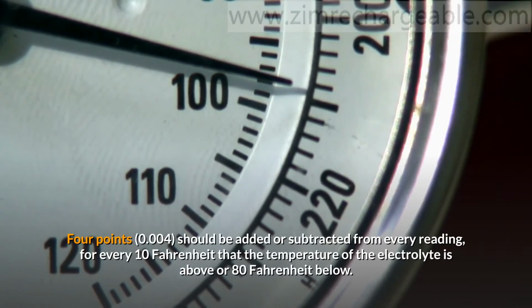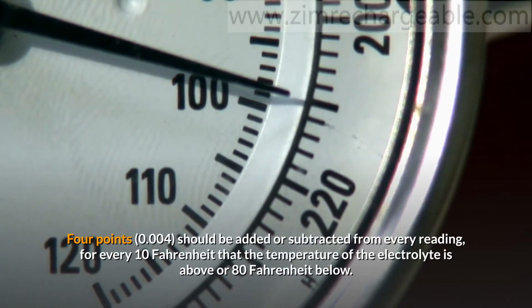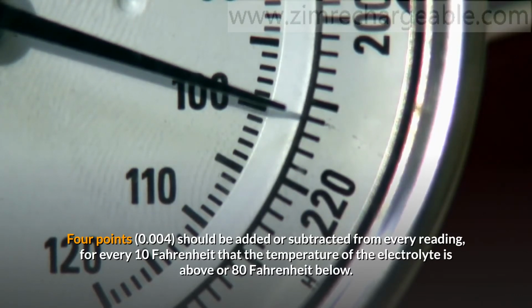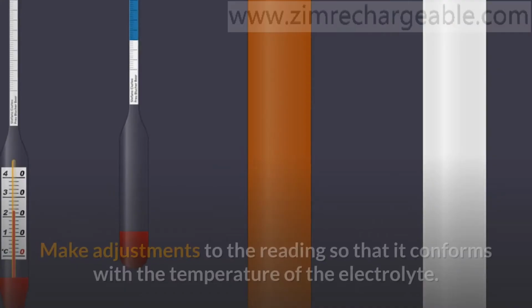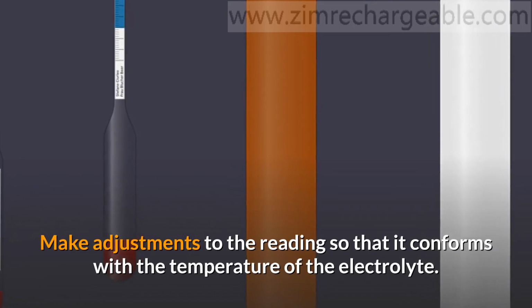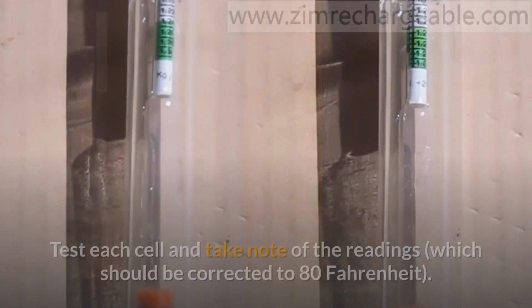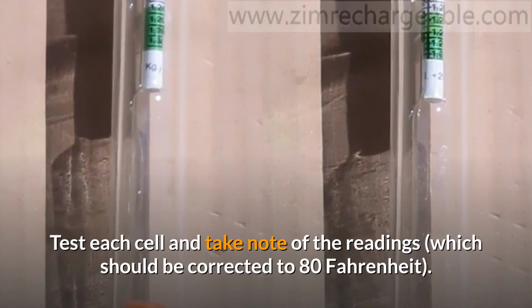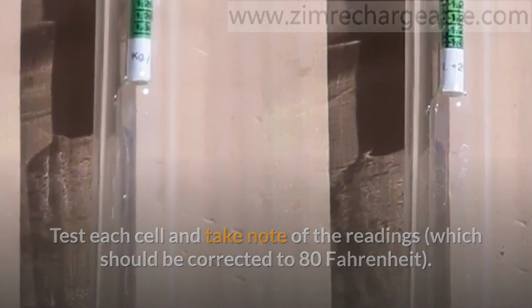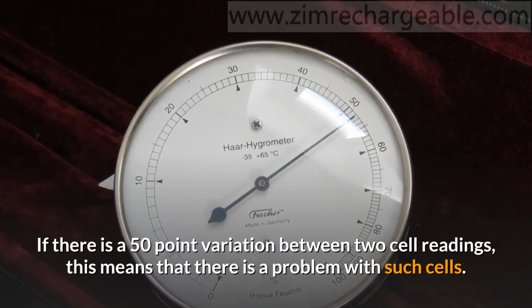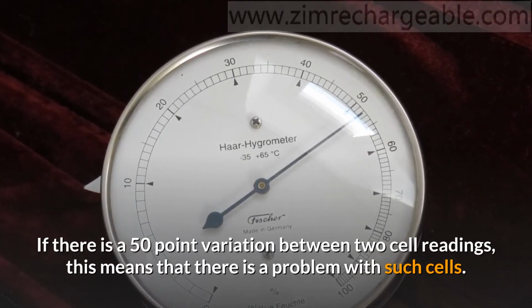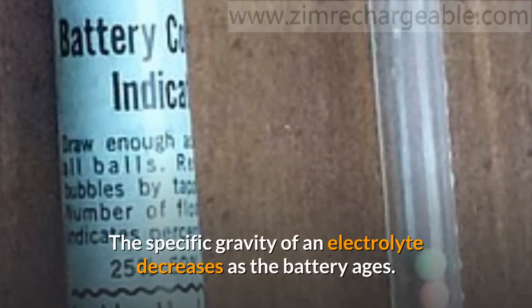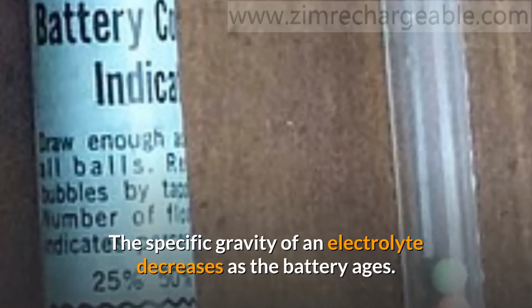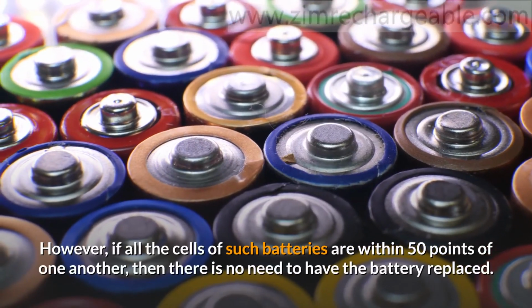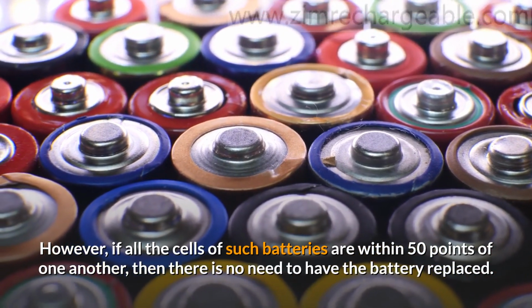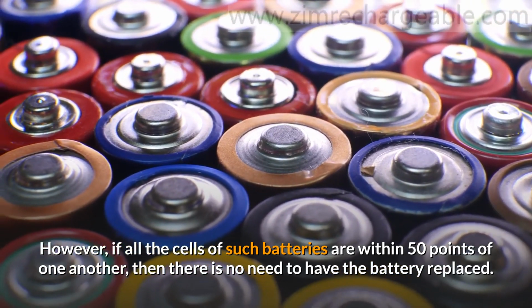0.004 should be added or subtracted from every reading, for every 10 degrees Fahrenheit that the temperature of the electrolyte is above or below 80 Fahrenheit. Make adjustments to the reading so that it conforms with the temperature of the electrolyte. Test each cell and take note of the readings, which should be corrected to 80 Fahrenheit. If there is a 50-point variation between two cell readings, this means that there is a problem with such cells. The specific gravity of an electrolyte decreases as the battery ages. However, if all the cells of such batteries are within 50 points of one another, then there is no need to have the battery replaced.